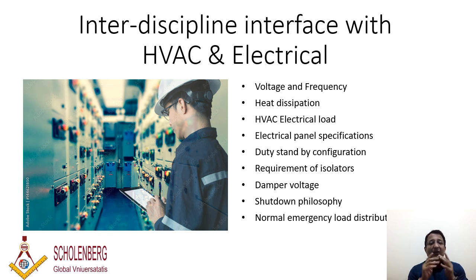Simple things: voltage and frequency. Voltage is essential - 400 volt or 690 volt - because 400 volt is LV, low voltage, and 690 volt becomes MV. So the selection of motors is different. We need to always ask them what voltage the entire platform is considering, whether LV or MV, because based on that your entire HVAC system's electrical aspect is going to change.